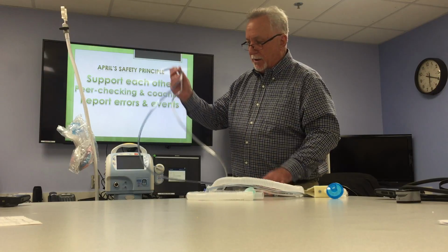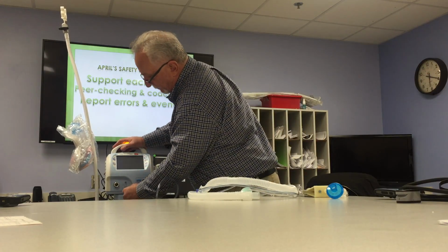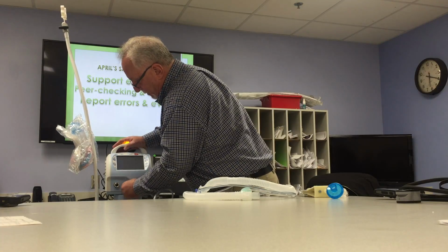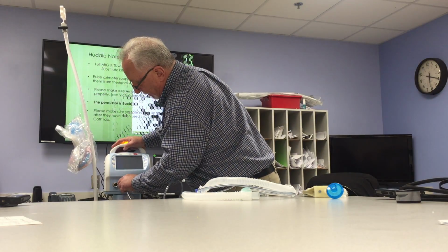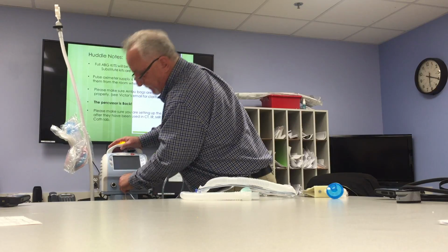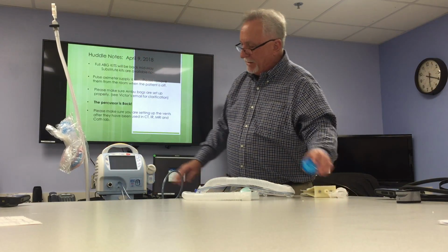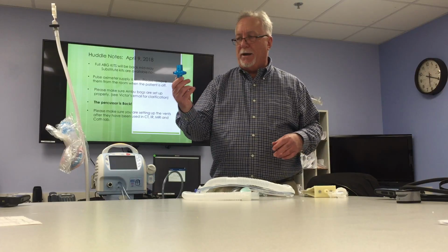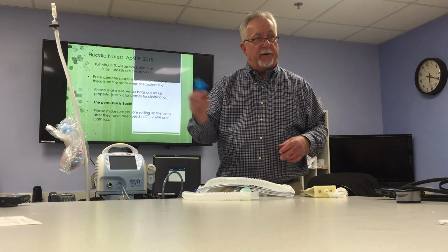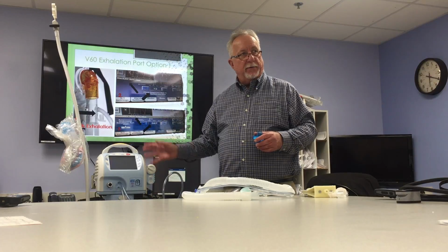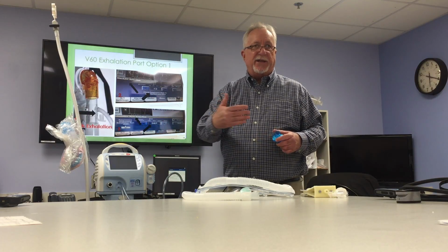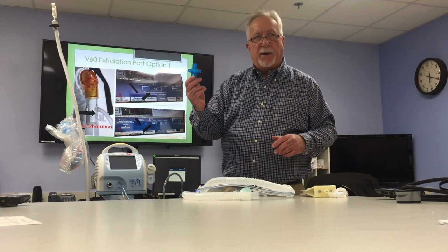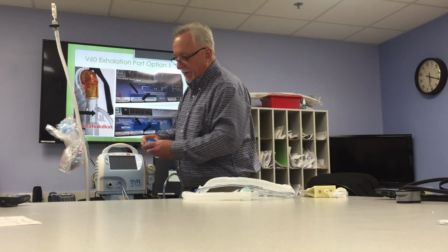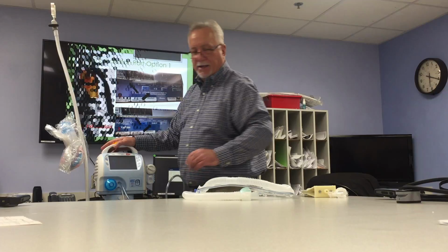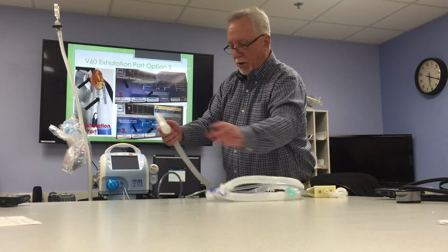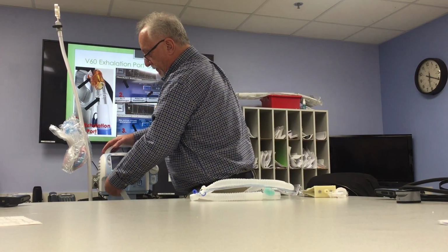All right. So what we're going to do is hook up our small tubing. We put the smaller tubing on the small post, the larger tubing on the large post, and you can't interchange them. Won't allow you to do that. And then on your outlet here, I would prefer that you use some sort of filter, because you are entraining ambient air into the ventilator that's then going to the patient. So you probably already do that on your ventilators. Just add a filter that protects your patient a little bit more. Attach your large bore tubing. Okay.